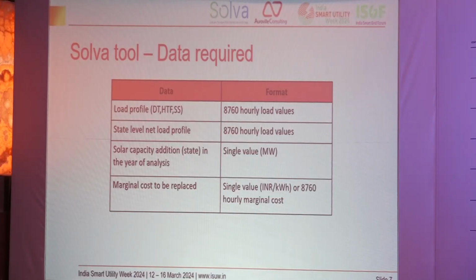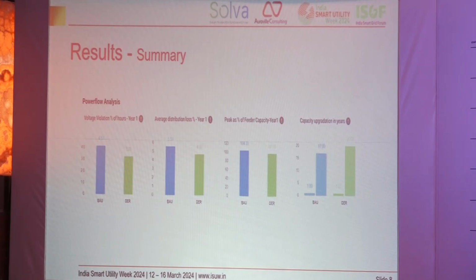To show how the results are generated from the tool, here is a summary of the results. We show four parameters of comparison: the percentage of voltage violation compared to the BAU case for year 1, the average distribution percentage loss compared to the BAU case, the peak capacity being taken by the infrastructure, and suggestions on how capacity upgradation would be required for this infrastructure.